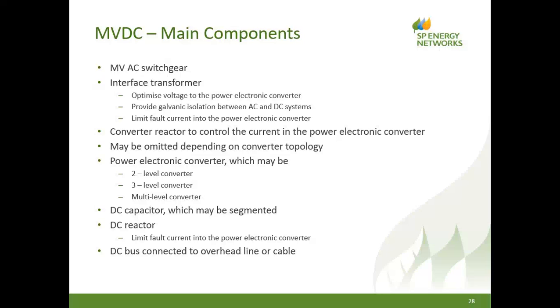The DC reactor, again, is there to limit fault currents. If we have a fault on the DC side of the converter, the remote converter will pump in fault currents, or will try to pump in fault currents. And again, the DC reactor will limit the fault current that flows into the power electronics. And the DC bus, as we've now described, can connect either to an overhead line or a cable. And for this Angle DC project, of course, we have both. So if we move on to the next slide.